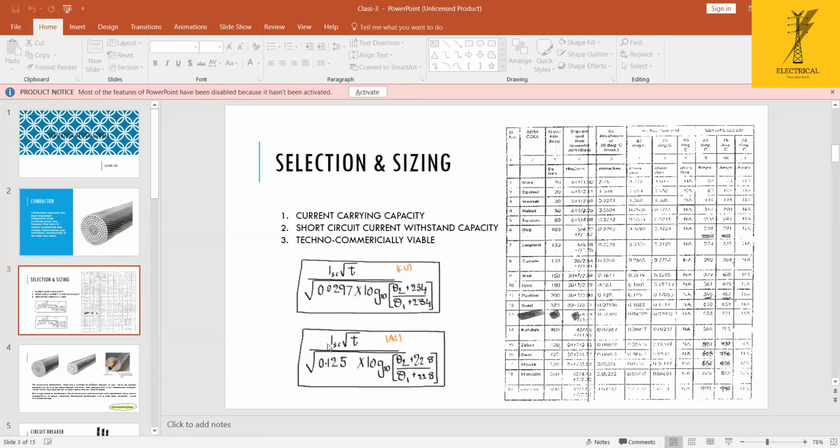And if you inject whatever current, suppose 40 kA, then you know, by injecting this 40 kA, what the temperature rise is, by some graphs. So by this, you will come to know the square mm of the conductor required. In a simple way, if you ask me, we will do it with a formula like ISC root T by K.